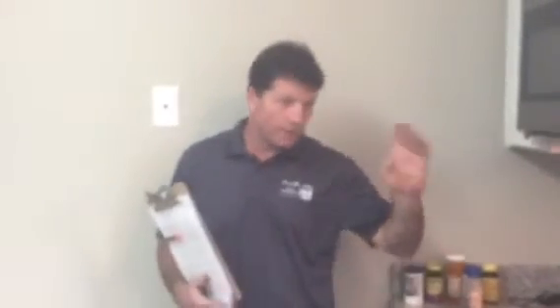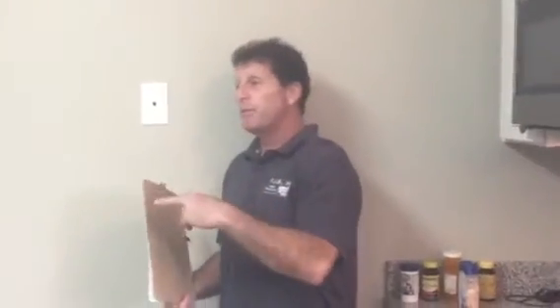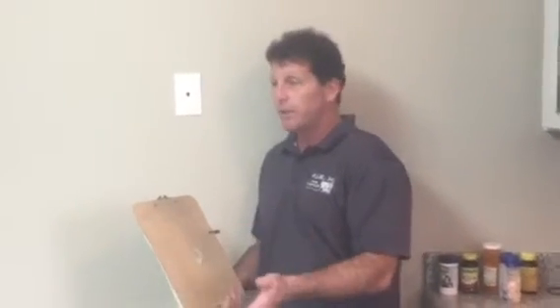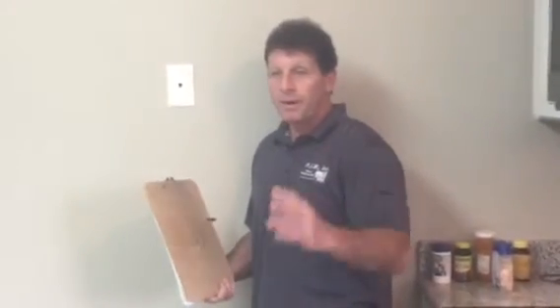So we had no reverse polarity or anything? No, in fact, I'm glad you mentioned that. They have ground fault protection here in the kitchen and at both bathrooms. In the 70s, that wasn't required, so you know that whoever was here installed that to upgrade those areas. So that's one less thing you have to worry about.